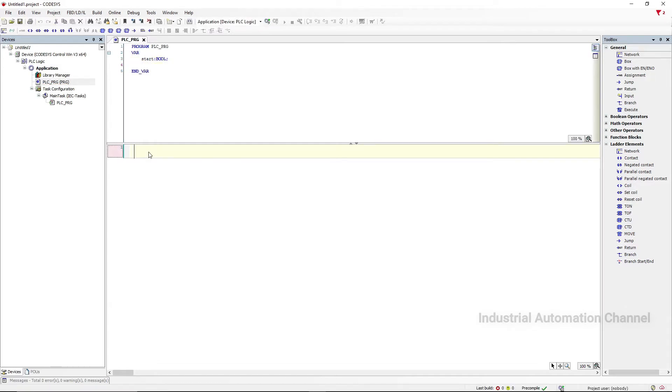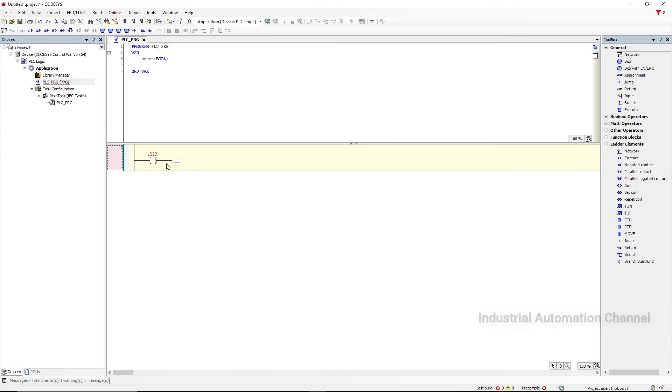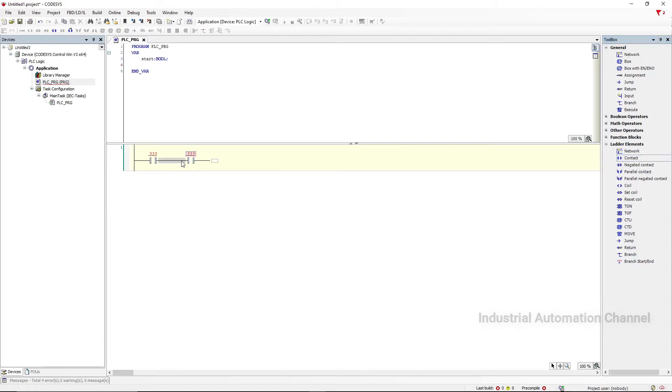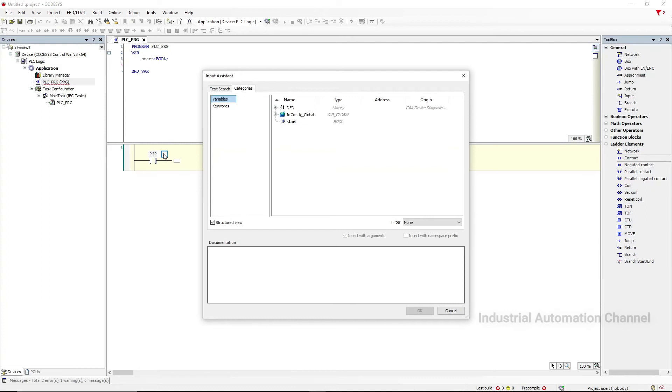I'm going to create a very simple project. I want to turn on and off an output with a push button. Insert a normally open contact. You can insert it by clicking on the contact icon or drag and drop. In this green box I want to use my variable that I have already defined. Click on here and from the variable list select Start.